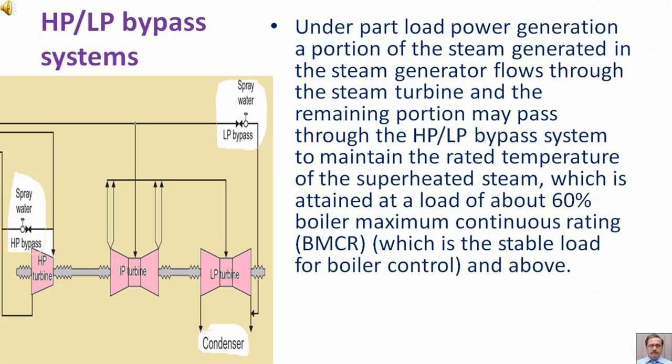Under part load power generation, a portion of the steam generated in the steam generator flows through the steam turbine and the remaining portion may pass through the HP-LP bypass system to maintain the rated temperature of the superheated steam, which is attained at a load of about 60% boiler maximum continuous rating, which is the stable load for boiler control and above.